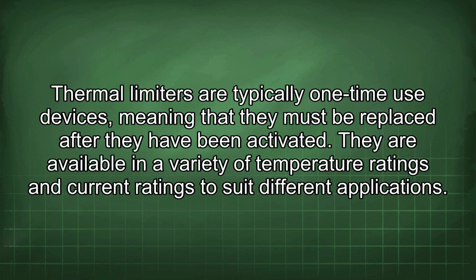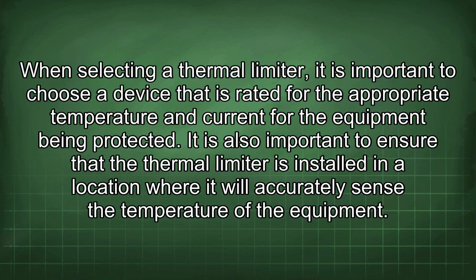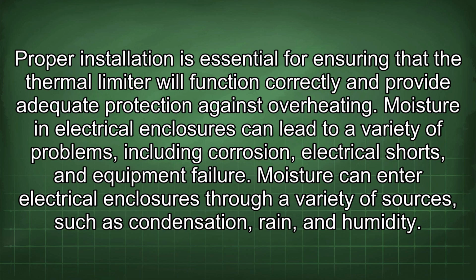Thermal limiters are typically one-time use devices, meaning that they must be replaced after they have been activated. They are available in a variety of temperature ratings and current ratings to suit different applications. When selecting a thermal limiter, it is important to choose a device that is rated for the appropriate temperature and current for the equipment being protected. It is also important to ensure that the thermal limiter is installed in a location where it will accurately sense the temperature of the equipment. Proper installation is essential for ensuring that the thermal limiter will function correctly and provide adequate protection against overheating.